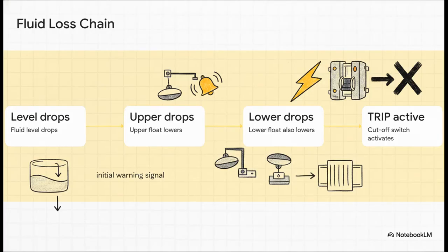The escalation here is totally sequential. First, as the fluid drops, the upper float goes down. That's your initial warning. But if the leak is severe and the fluid keeps dropping, that lower float gauge inevitably falls too. And when that lower float drops, it activates a secondary, much more critical reed switch. This is a cutoff contact, and its job is to immediately trip the system.